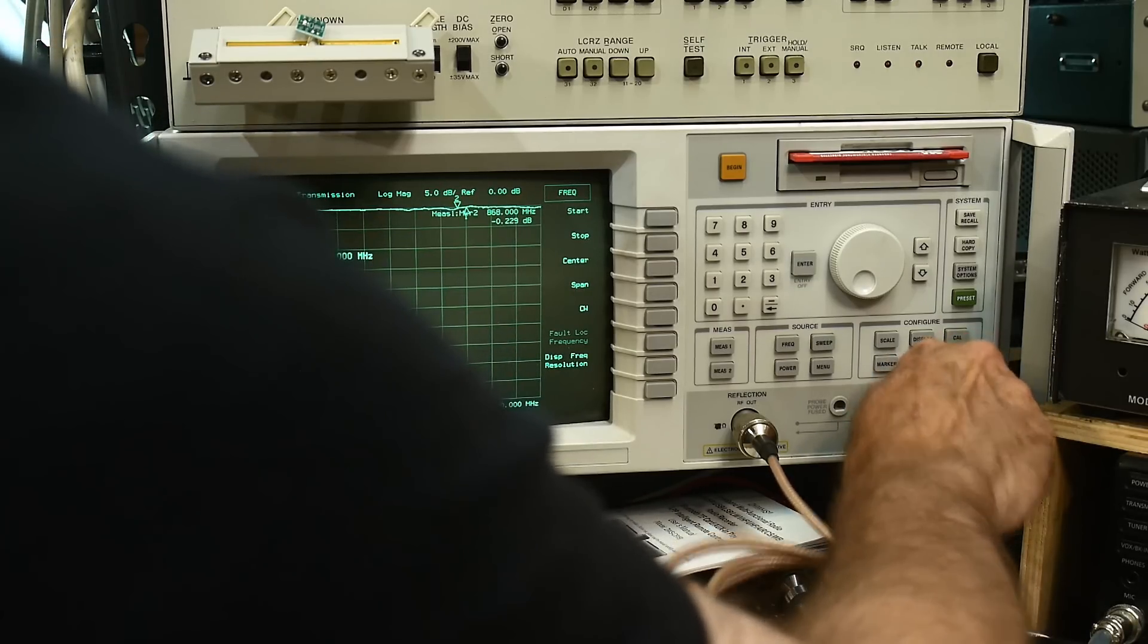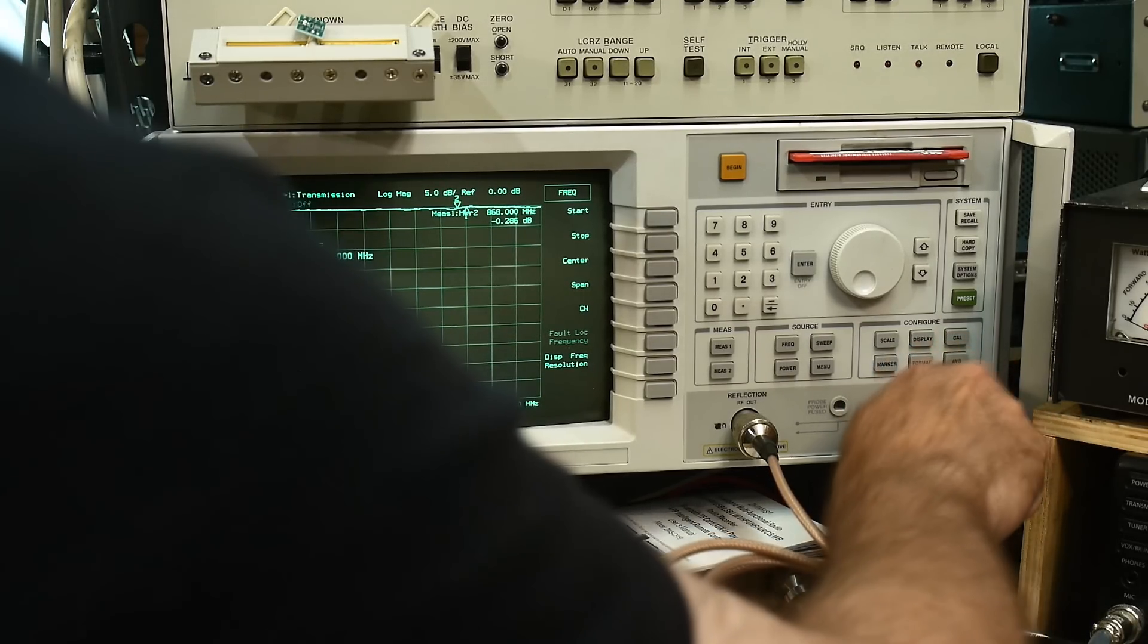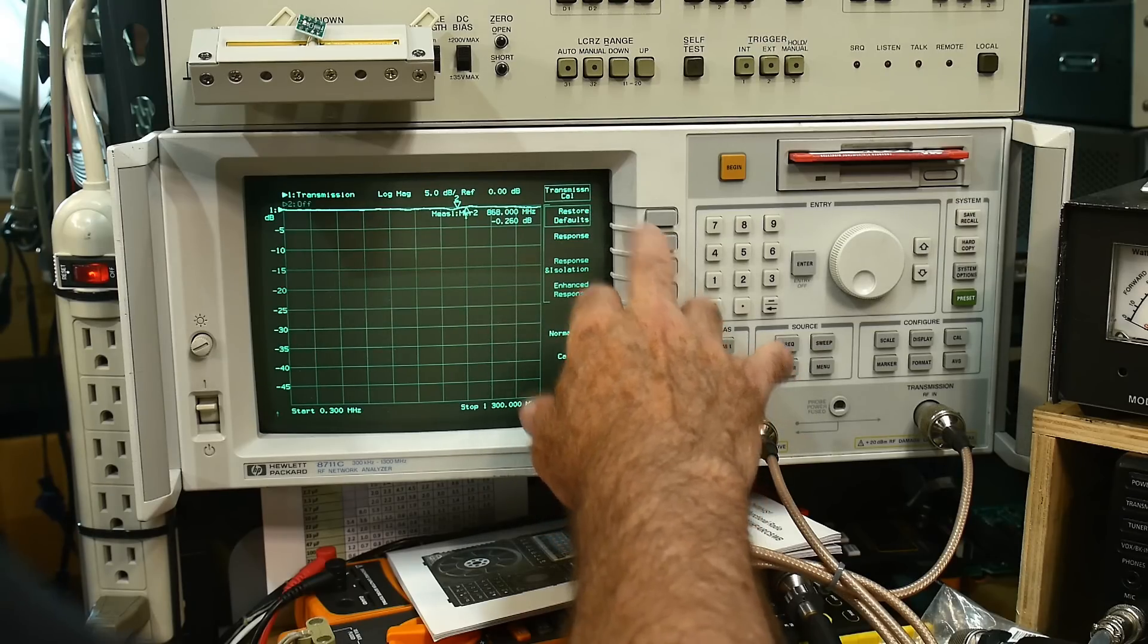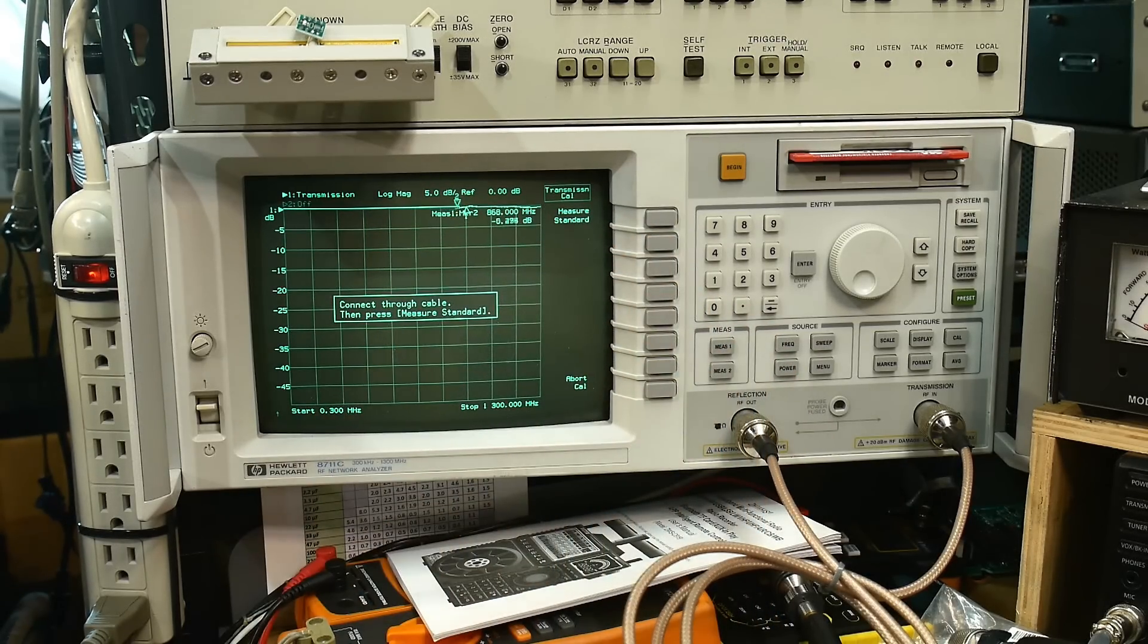Even without a calibration, whatever is in there. Yeah, that looks like it's through. Cal will do a response curve. There we go. It's nice and straight now.